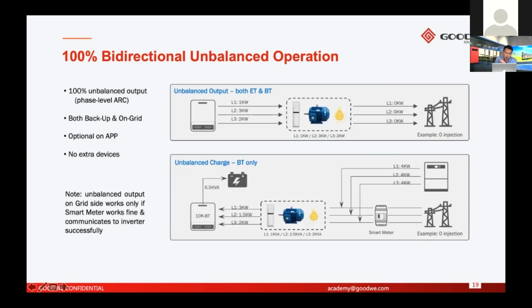And except for unbalanced output functions, we have already developed another function. We call it Imbalance Charge. Imbalance Charge is only realized on the BT series, because it is only available for AC coupled. It's not for hybrid, because hybrids can connect to PV and the PV can charge the battery, right? But AC coupled inverters have to work with on-grid systems, and the power that charges the battery mostly comes from the on-grid systems. But the on-grid system has to connect to the AC side first. So the battery charge for AC coupled inverters is actually from the AC side to the DC side, then charges the battery, right?